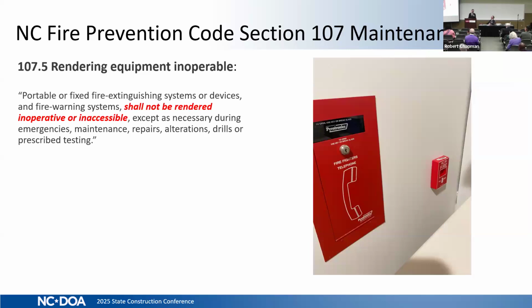All right, we see here a firefighter's phone and a fire alarm manual pull station. It needs to stay running. You can't take it down. You might say, hey, well, our fire alarm system is one of those that went obsolete. We're going to be down for about 2 months. What can we do? Obviously, in that case, you would need to implement a fire watch, and that has to comply with the OSFM requirements. Right. And also take note that it has to be accessible. It can't be rendered inaccessible, because this next slide kind of touches on that.